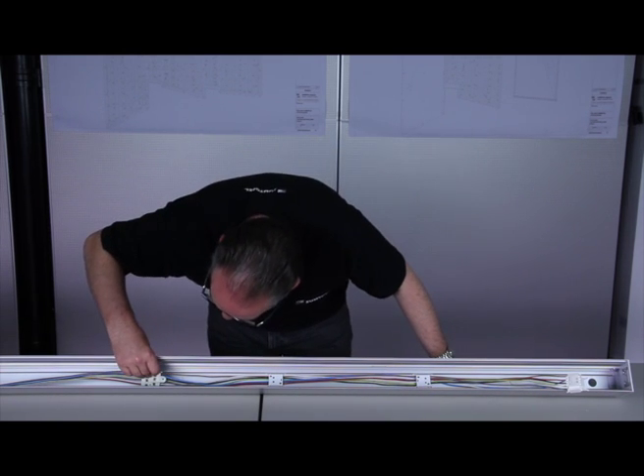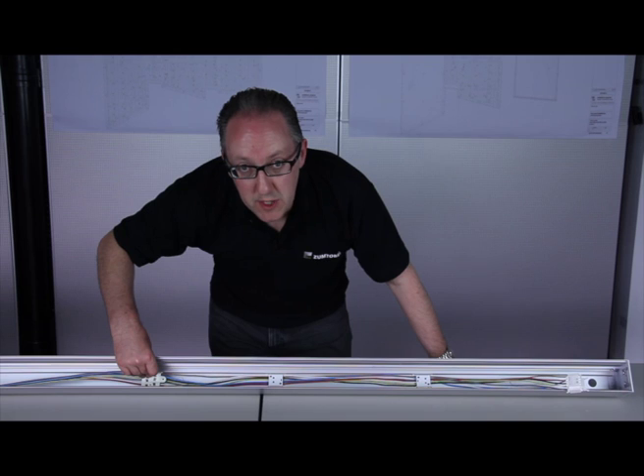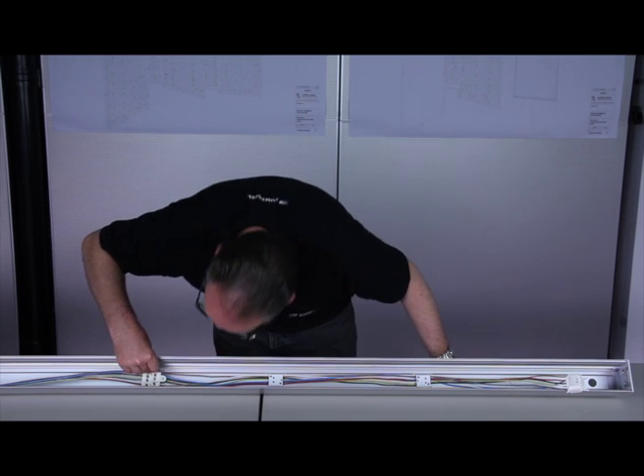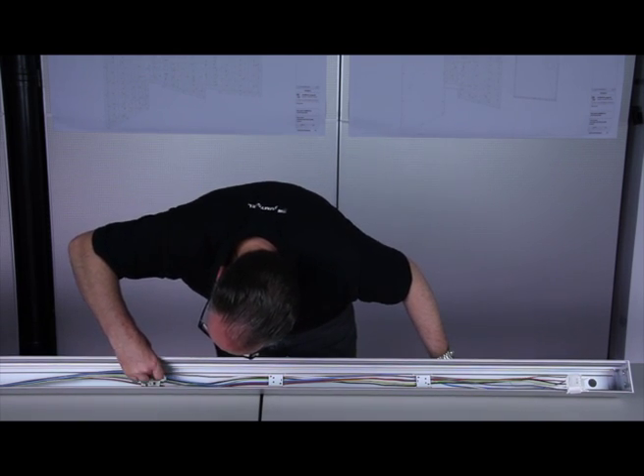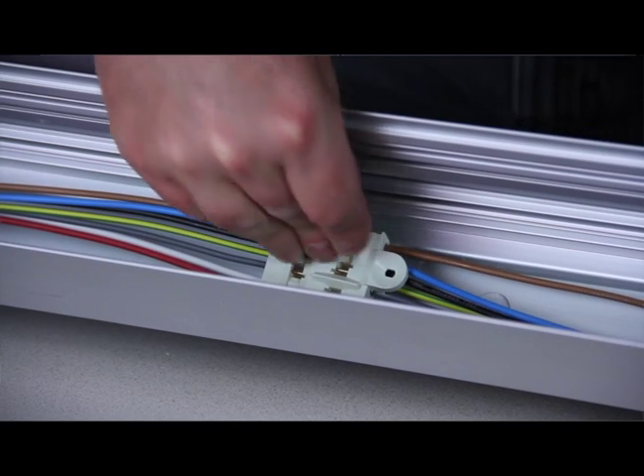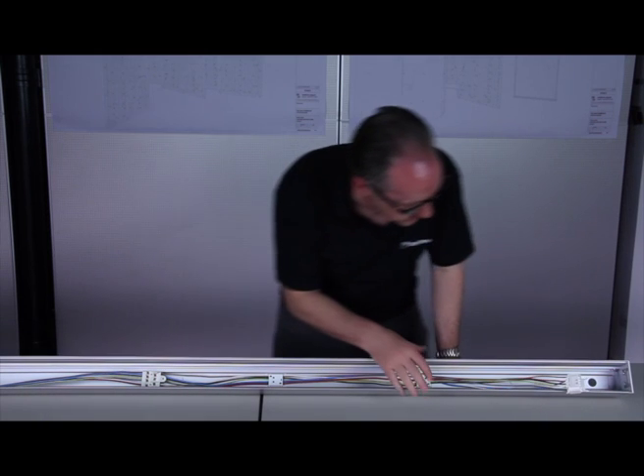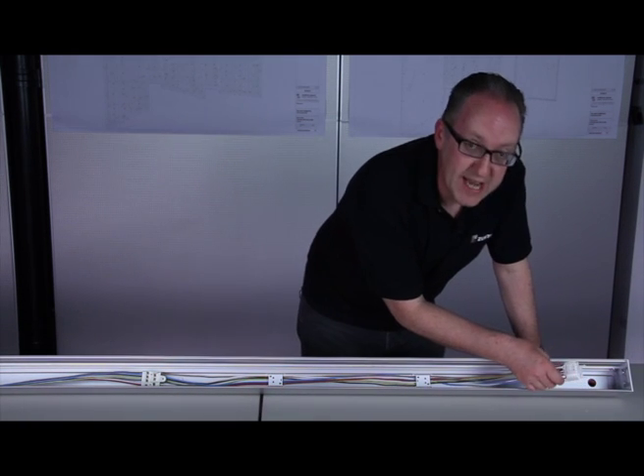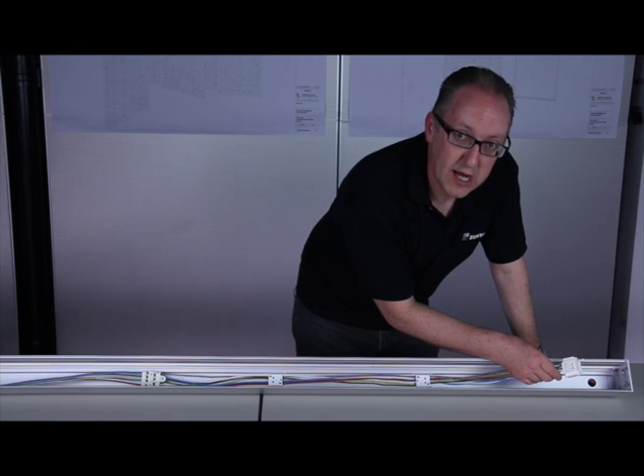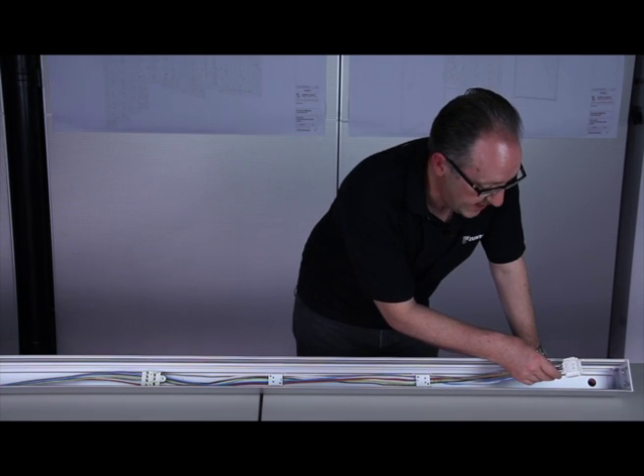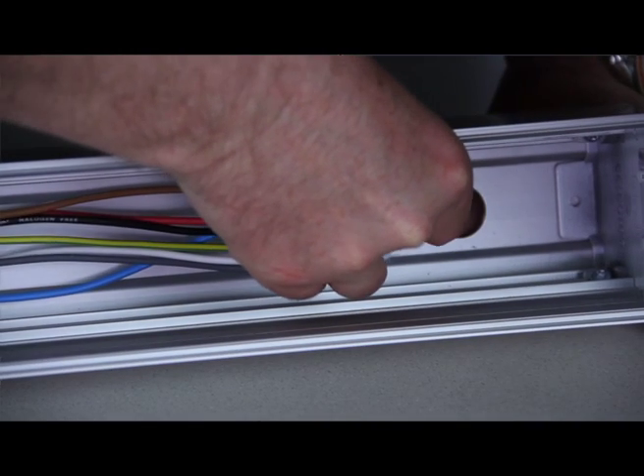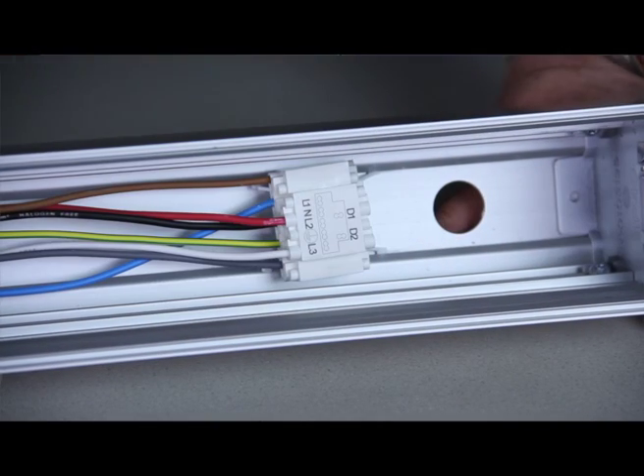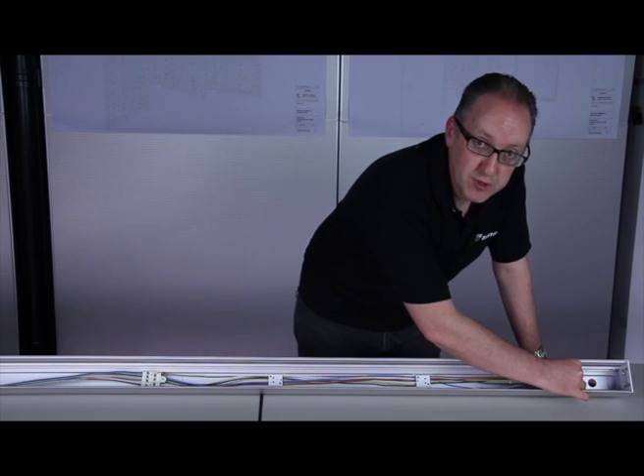Then the socket on the wiring loom that coincides with the plug on the gear tray is clipped into the back of the extrusion at the position previously marked. At the live feed in, the cables are cut to the right length, made off, wired into the live feed, and that also is clipped into the back of the extrusion.